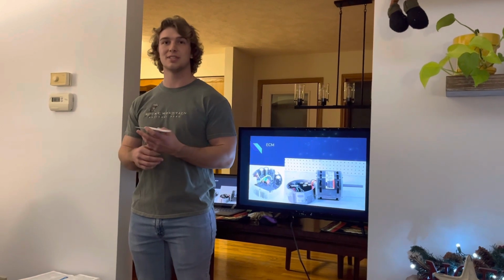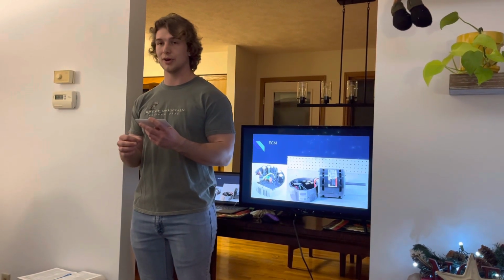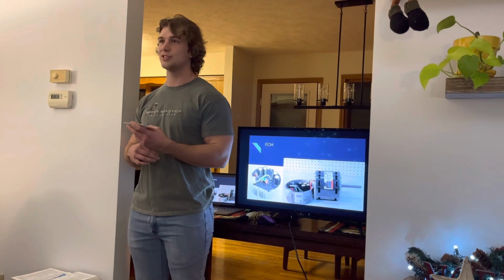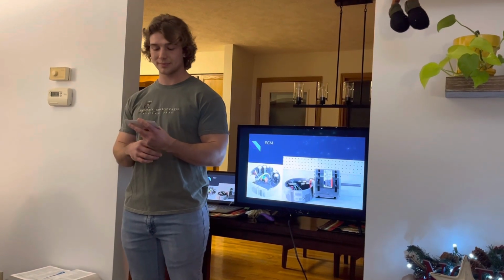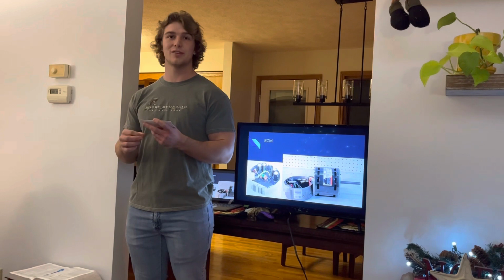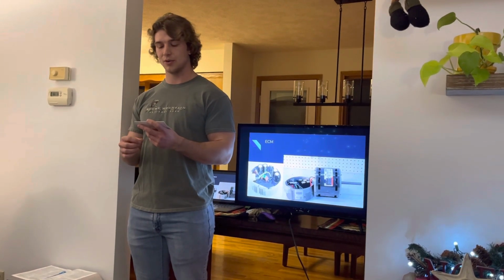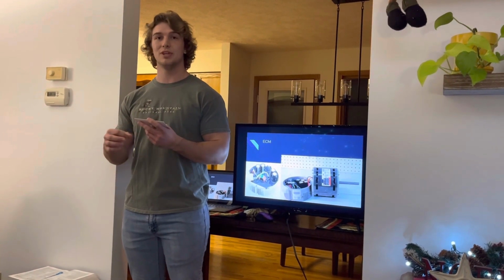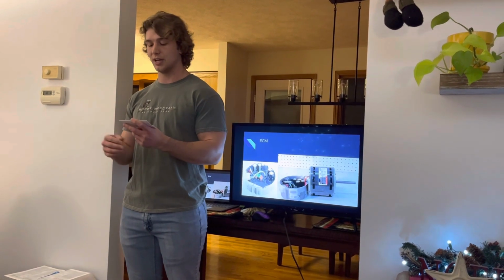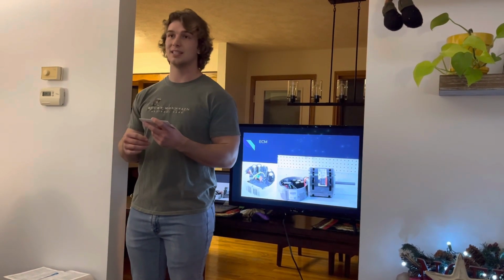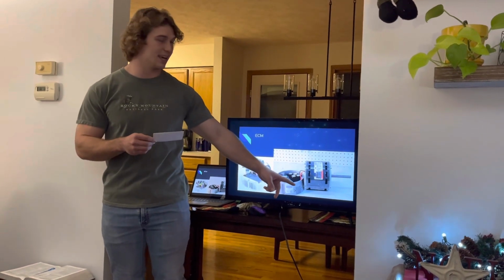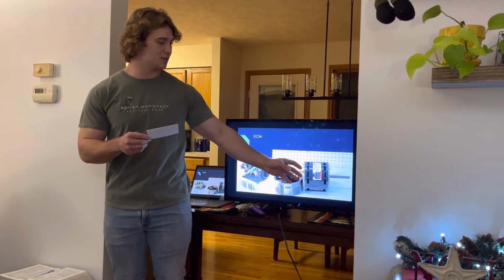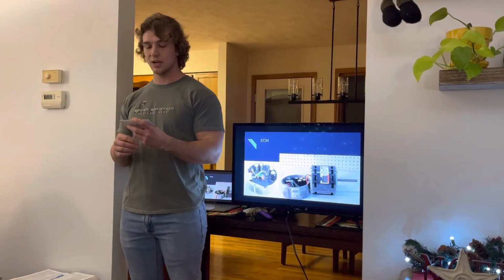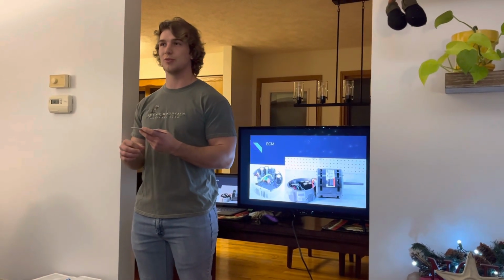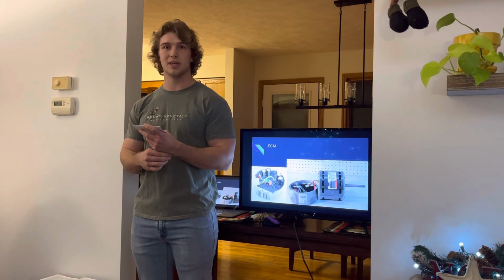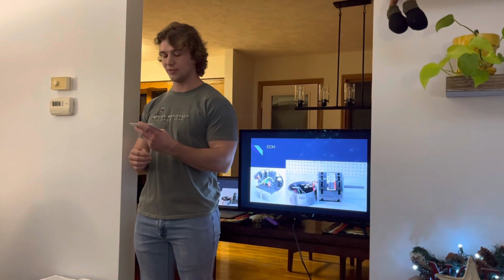Now, an ECM stands for an electronically commutated motor, and these motors have taken over as industry standard within the last few years. The old standard mechanically commutated motors, or MCMs, required a capacitor and received complete voltage from start until finish. An ECM contains a microprocessor which is located in the head unit of the motor, which mounts up to the motor. With the use of this microprocessor, it allows for the motor to more accurately manage the magnetic field within and utilize your electricity more efficiently.